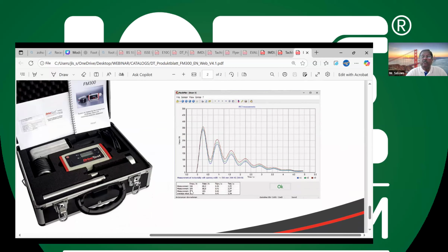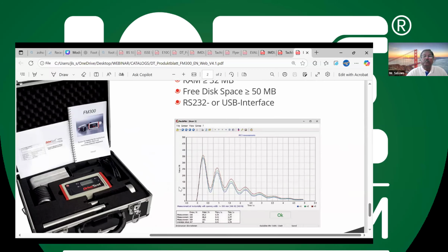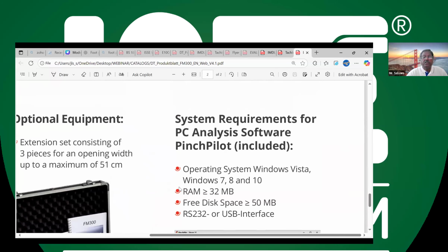It should be less than 150 newtons, but the reading indicates around 300. Normally during usage, the force can increase because of wear and tear of the roller, so it will be very high. I have seen this in Dubai and elsewhere. I have measured in some metros also, more than 300 newtons, because people will be running and trying to enter at the last moment. Sometimes people say the light curtain is there and it will open. But the light curtain has a blind area, maybe in the last 100 mm when the door is closing, where it cannot work. I think elevator engineers can say better. If you put a hand in that area, the door cannot reopen, and it can cause injury if the force is more than 450 newtons. It's only by chance.